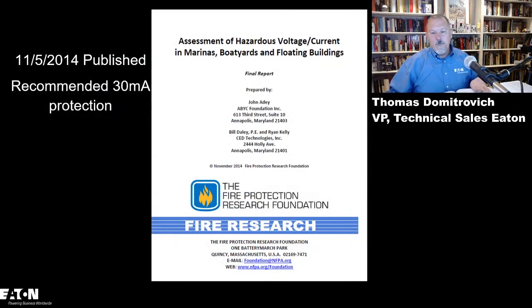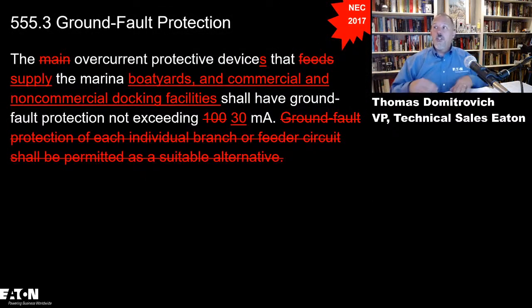And then what they did was they went back to this newer Marina risk reduction document, and basically the code changed and said all overcurrent devices had to have 30 milliamp ground fault protection of equipment. So it went down instead of up. But what I think you will be pleased with is what we did in 555 with regard to a tiered approach. So this is what was the change in the 17.